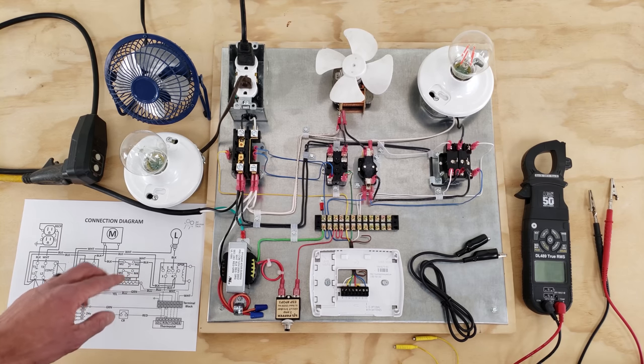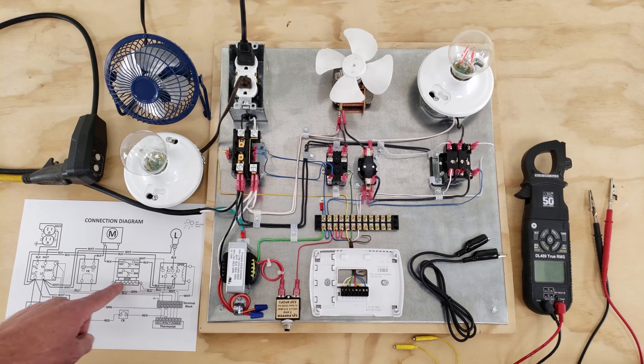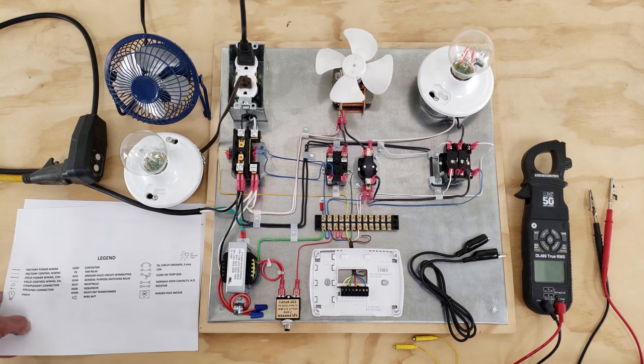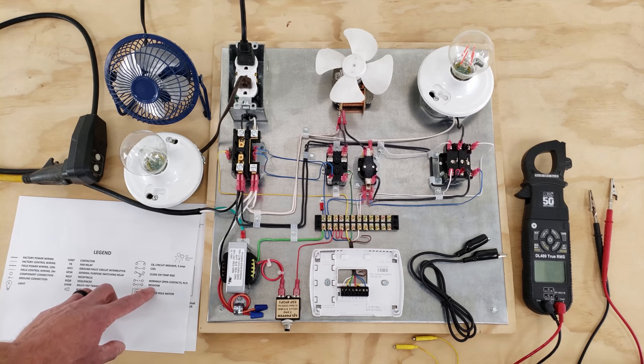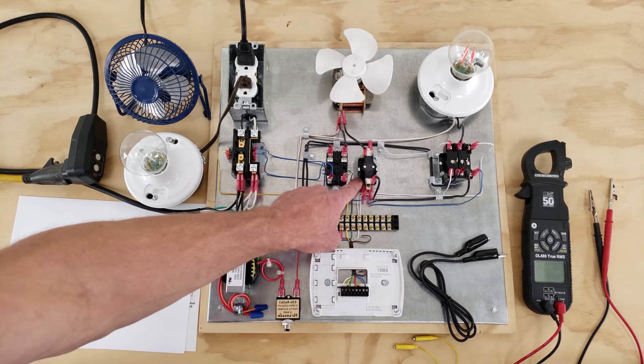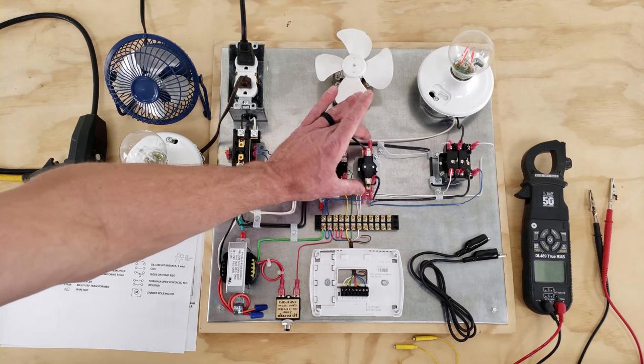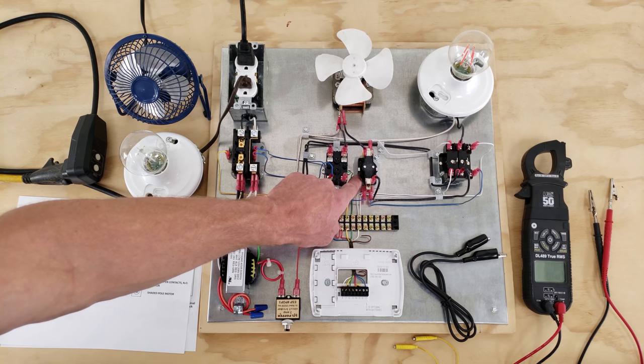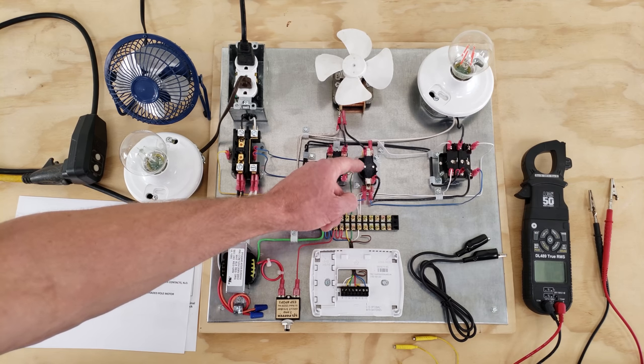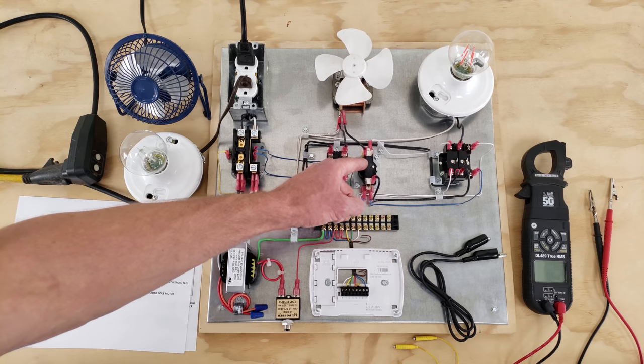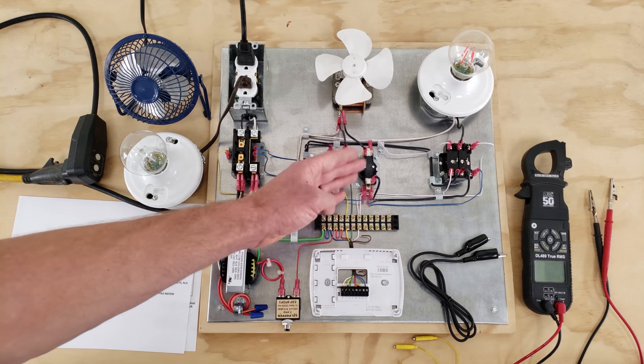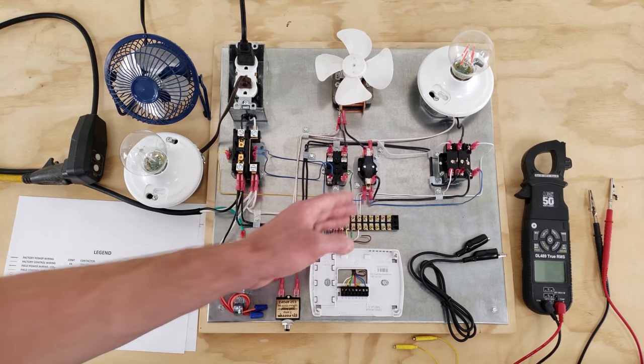two-section sequencer, but the issue with this is we're not using the lower section, we're just using the top one due to the timing mechanism. And so you see on the bottom right here of the sequencer, there's a resistor. You look at your legend right here and you see there's a resistor. So you have a pan heater on the bottom. Anytime you send 24 volts in the bottom of a sequencer, you have a pan heater that's heating up a bimetal disc, and it's going to push up on rods, and that's going to connect one of these levels at a time, and then it's going to disconnect one of the levels at a time as it cools down.